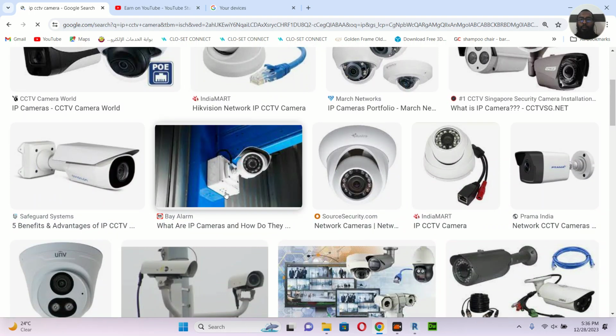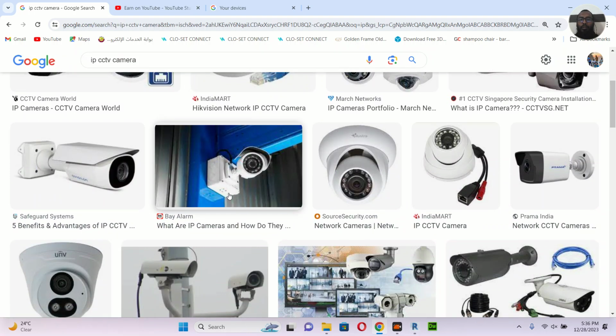You see here this back box. So this back box will have one data cable like Cat6 or Cat6A. It depends. So from the panel, like a CCTV rack, sometimes it will go direct to the IDF panel. So it depends on the design. So from, let's say, the CCTV rack, there will be one Cat6 cable from the switch through the conduit. It will come up to the junction back box. So from there they will connect to the camera.